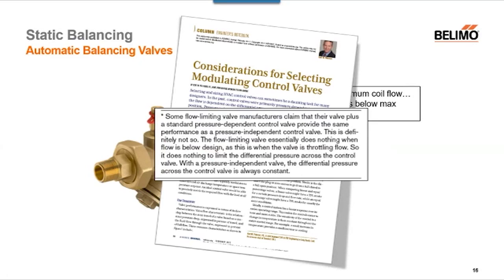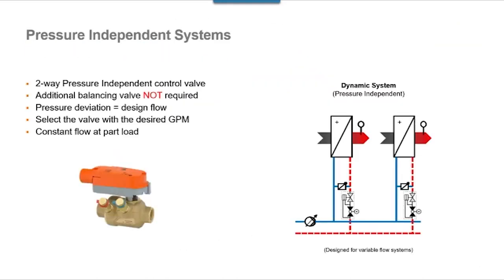It is not so. The flow limiting valve essentially does nothing when the flow is below design. That is, when the control valve is throttling. So you're still going to get the pressure effects across the control valve with the increase and decrease in flow. But the one advantage, I guess I'd say, you shouldn't really be getting more than the maximum flow you have set through that flow limiting device. But it is not the same as a pressure independent control valve.